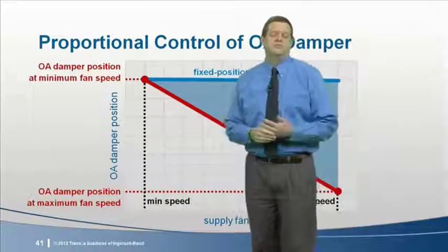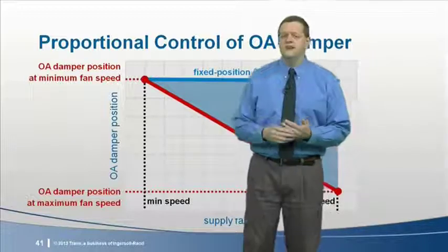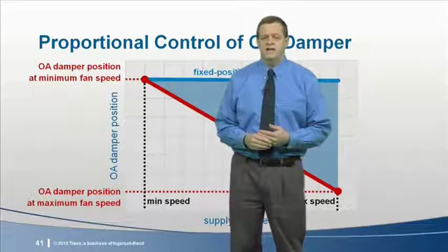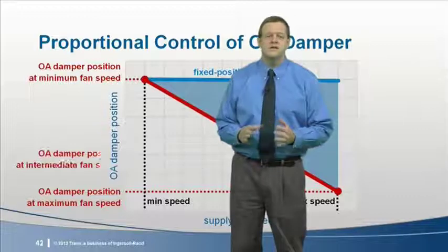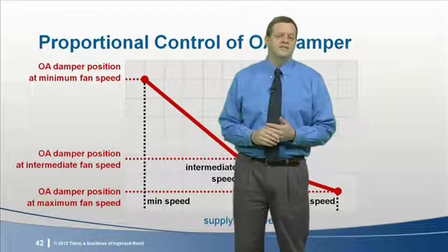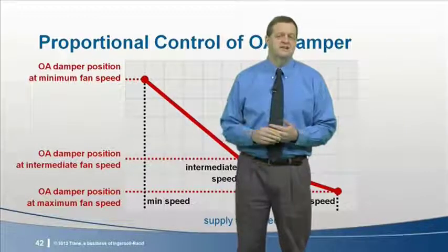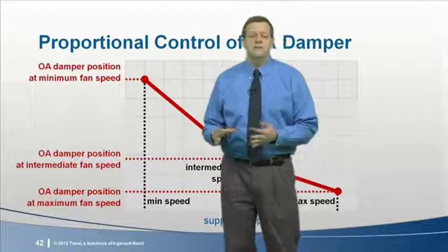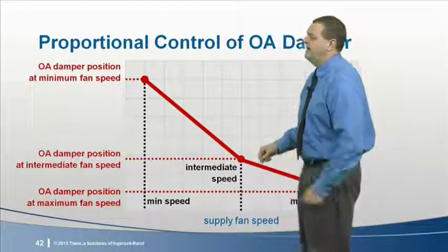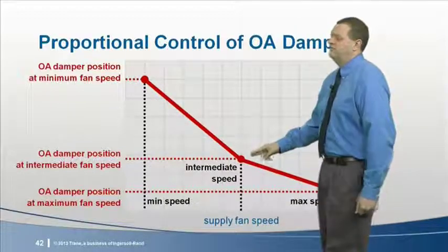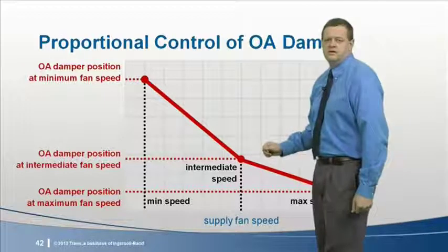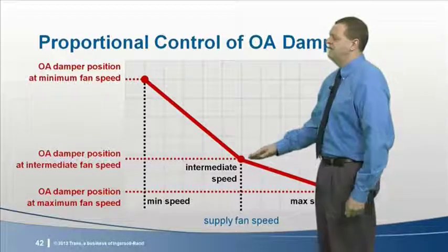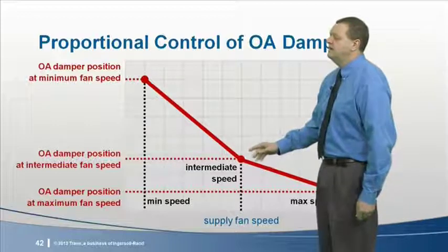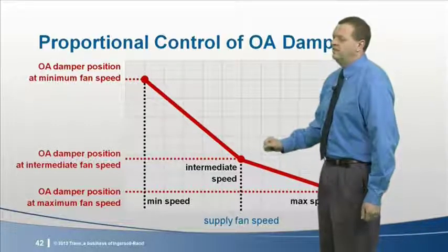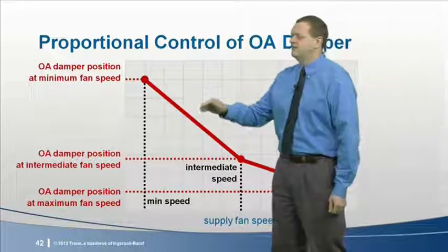Plus, it's relatively inexpensive, so it's used in a lot of smaller single-zone VAV applications. I mentioned that there is some inaccuracy since damper performance is nonlinear. One way to minimize this inaccuracy is to add a third damper position set point at some intermediate airflow. This ensures proper ventilation at this intermediate speed and minimizes any overventilation by shrinking the ranges between these set points.